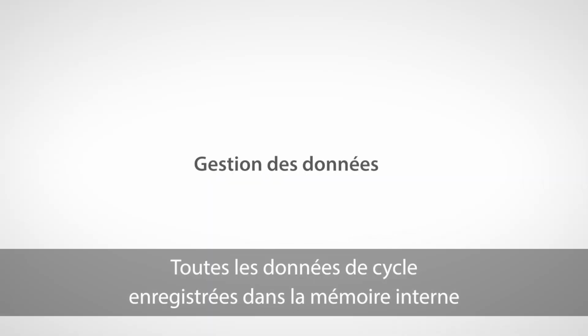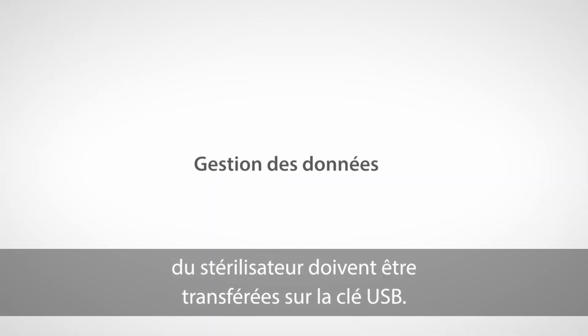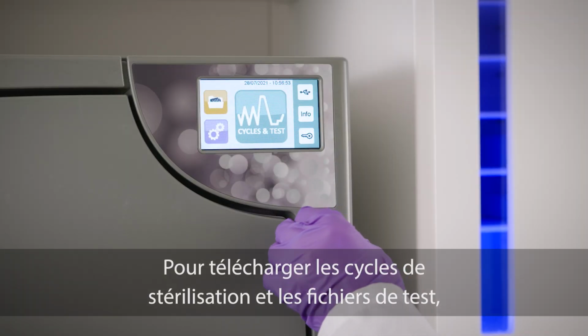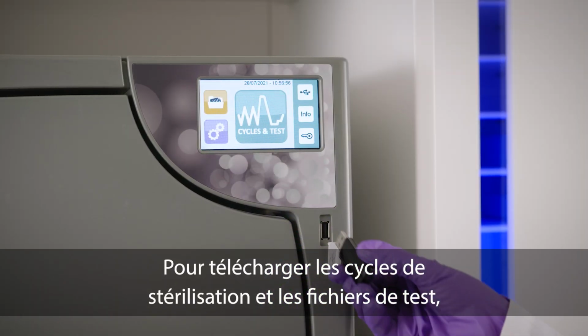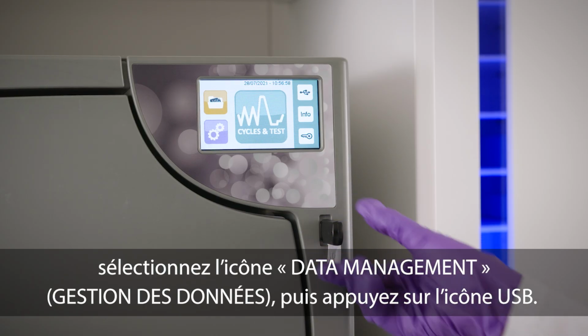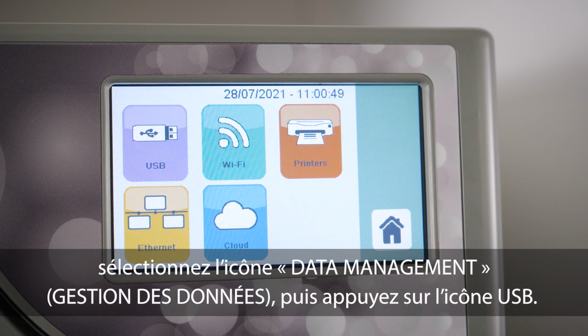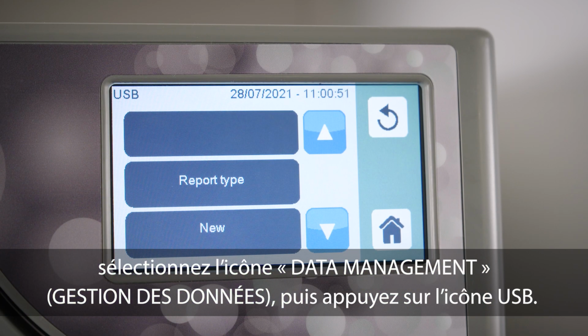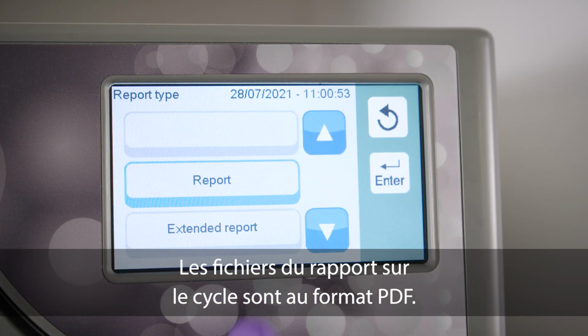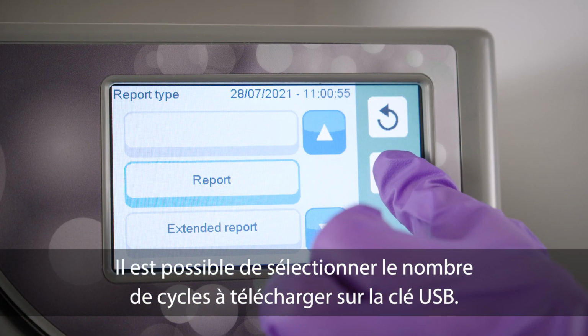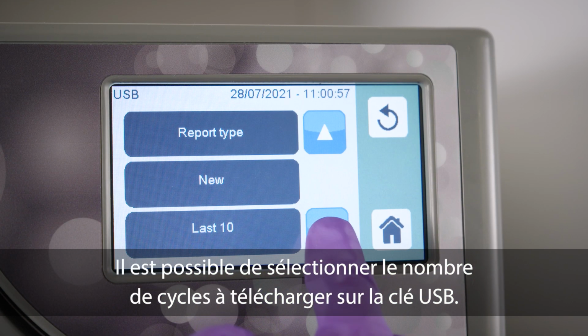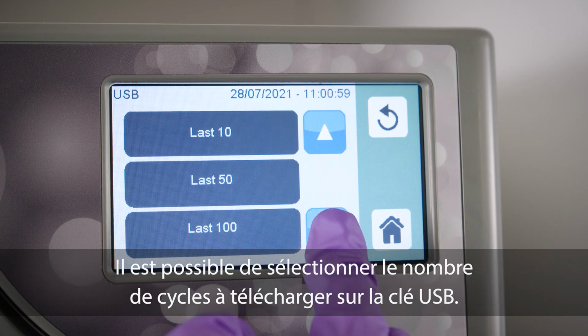All cycle data stored in the internal memory of the sterilizer should be transferred onto the USB. To download the sterilization cycles and test files, select the Data Management icon, and then press the USB icon. The cycle report files are in PDF format. It is possible to select the number of cycles to download onto the USB key.